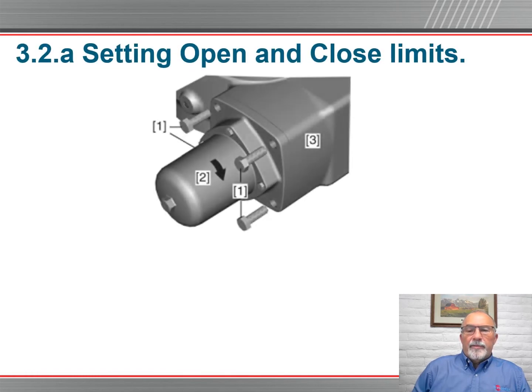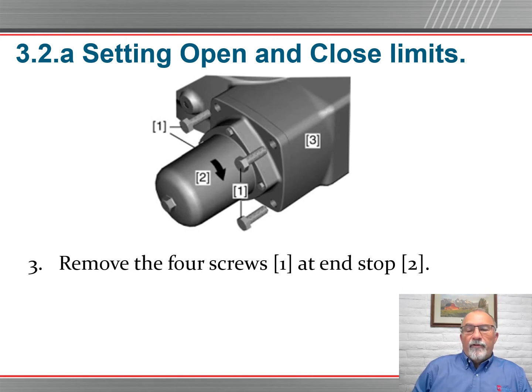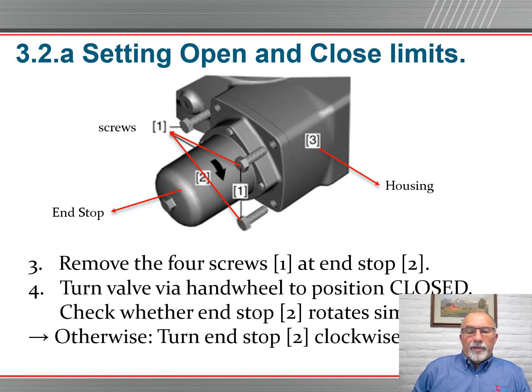Setting open and close limit switches or limits on your gearbox. Remove the 4 screws that are located as number 1 at the end stop number 2. You don't remove the end stop, you remove those and you just simply turn it until it hits its stop, and then back it to the closest hole alignment and replace your 4 bolts.